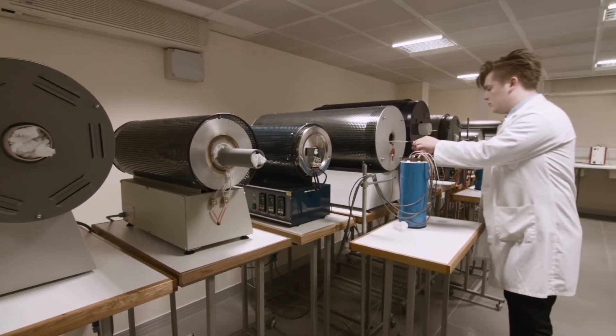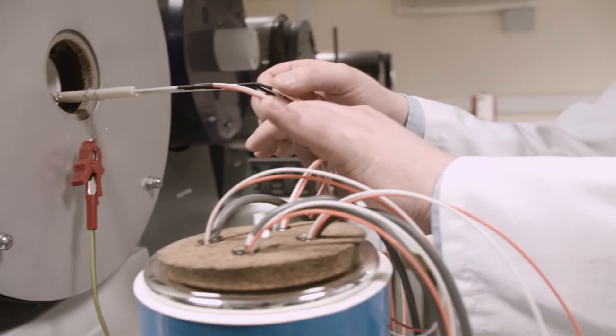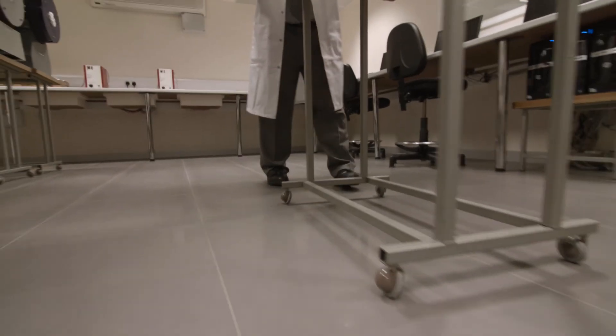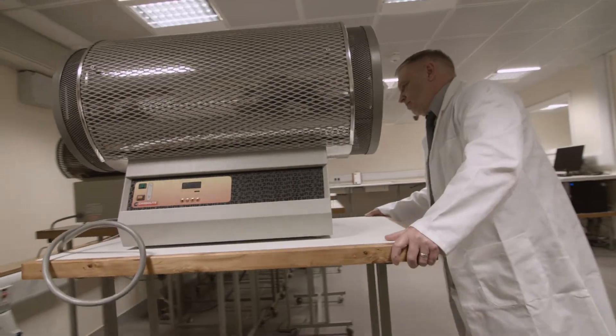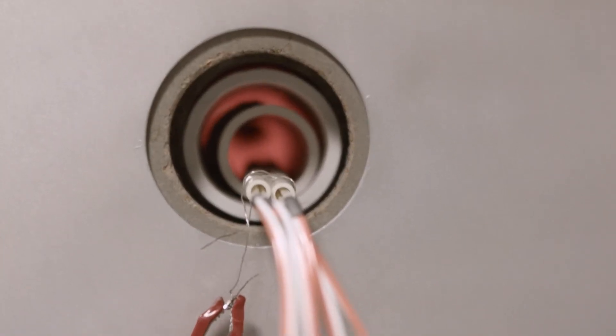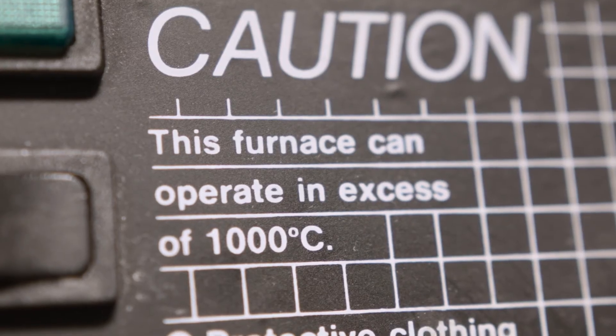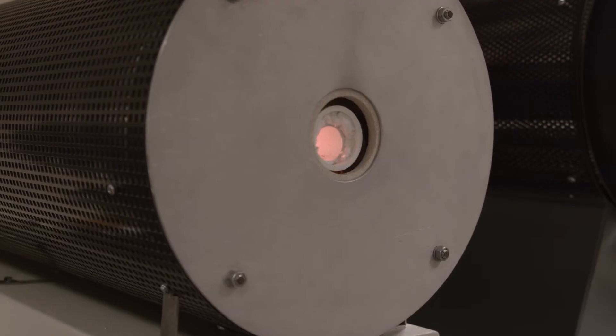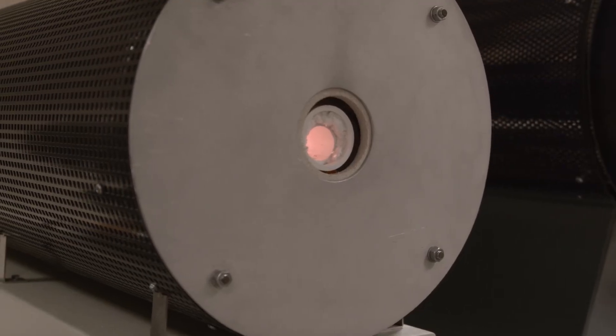There are 17 furnaces or test environments in this room, 10 of which are located on moveable trolleys which are used for thermocouple comparison calibrations. These furnaces enable the CCPI Europe lab team to conduct thermocouple calibrations and test at temperatures ranging between 50 and 1600 degrees Celsius. We can do this with any thermocouple combination and for almost every size of thermocouple construction.